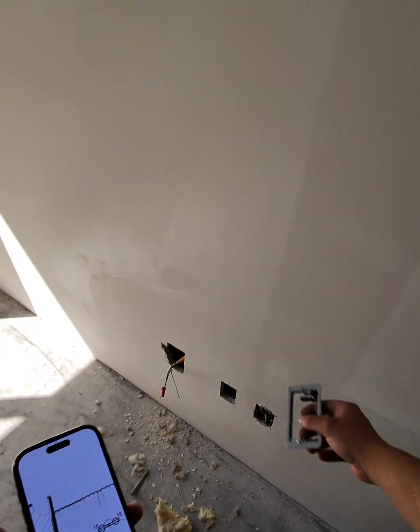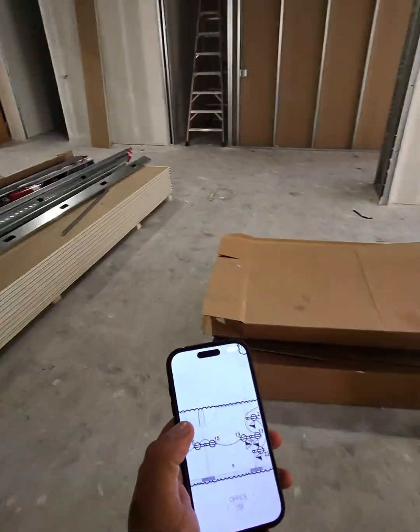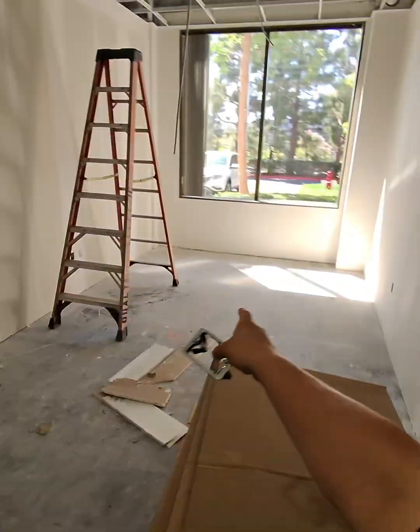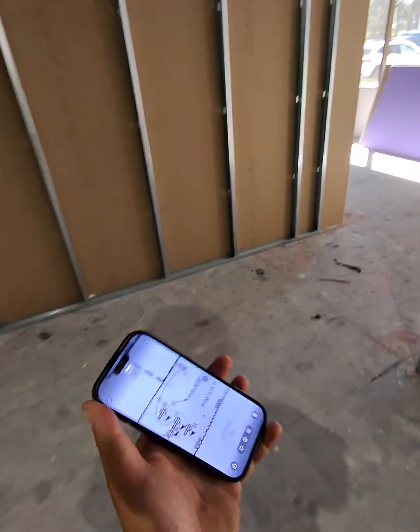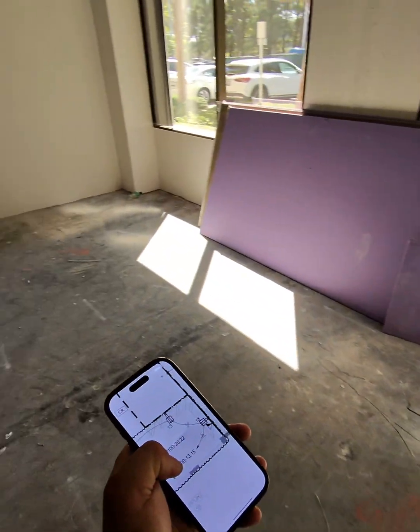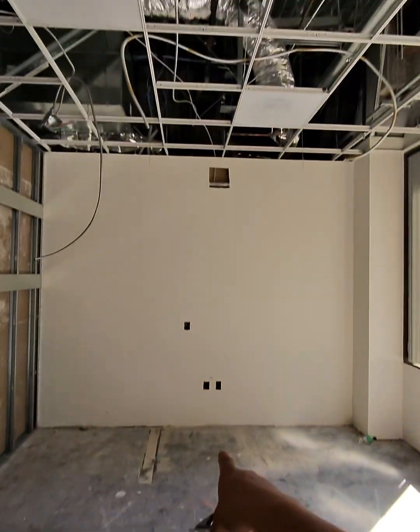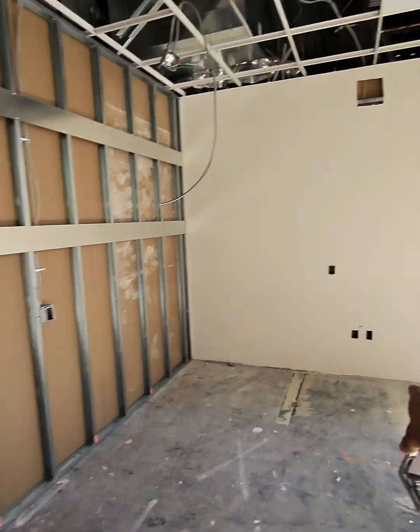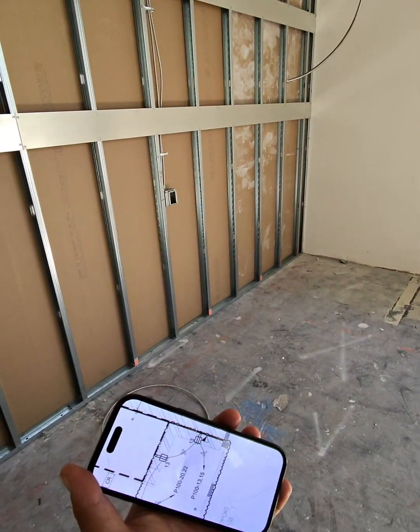So that's already installed. The outlet's installed per plan. Data ring, outlet, outlet. So that's good. Now this calls for 3 outlets, which it has, along with all the data rings. Data ring, outlet, but that's not installed yet. So I would need to install that cut-in.